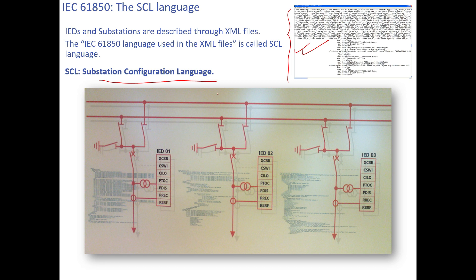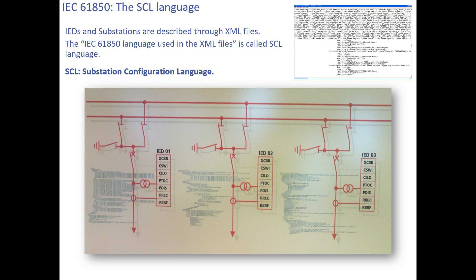All SCL devices and protection functions in 61850 are described through logical nodes, and these logical nodes are then mapped for substation automation in 61850. This is the same single line diagram considered in the first and second sessions — a 2-bus system with bus 1 and bus 2, three feeders with isolators, breakers, and CTs. Each feeder has one IED — an intelligent electronic device — which can be a BCU or protective relay.